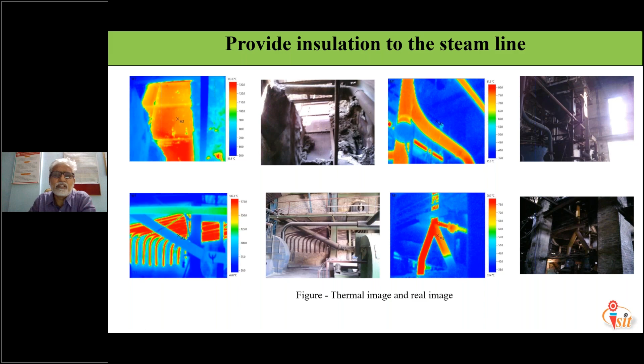Here is another example. While doing the energy audit, we use thermal imaging, or thermography. The novelty of this instrument is shown here: this is the thermal image and this is the real image. This figure is from a sugar factory. At a particular location in the factory, you can feel the heat radiating from the hot pipelines, but you cannot measure the temperature directly. So instead, we take the thermal image, and based on the thermal as well as real image, we can calculate how much heat is being lost because of radiation.